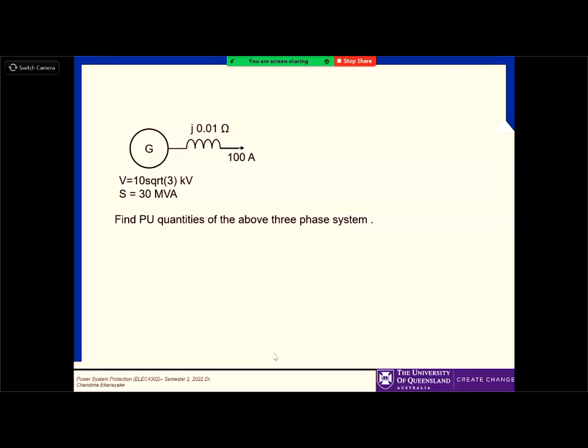And the other important thing is how do we select, when you have different base operating conditions. Sometimes, let's say you have a transformer which is 10 MVA, but your system base you selected as 100 MVA. Now you need to change the impedances of one system to another base. So there is some sort of base formula required to change the impedances from one setting to another.